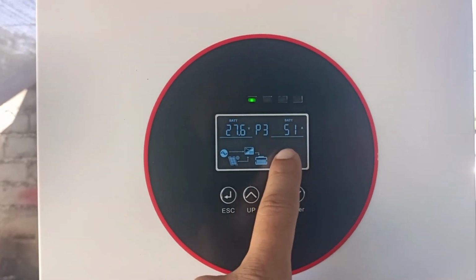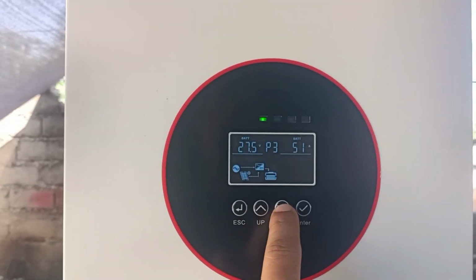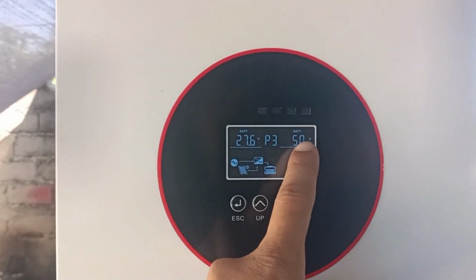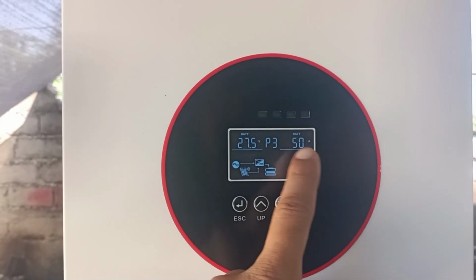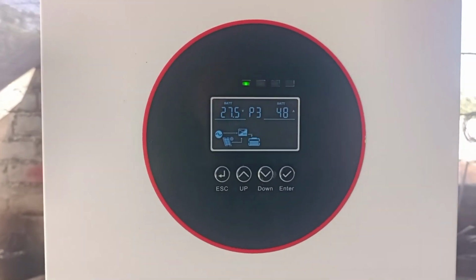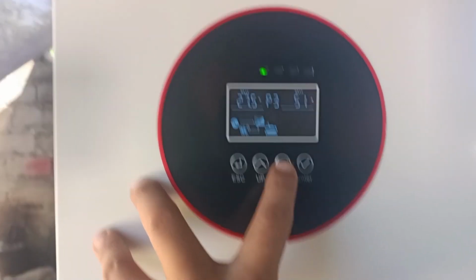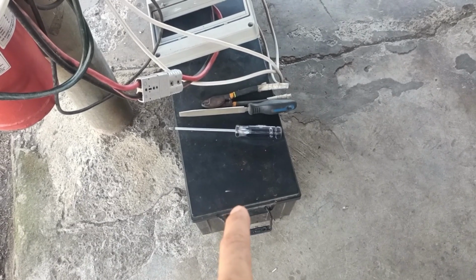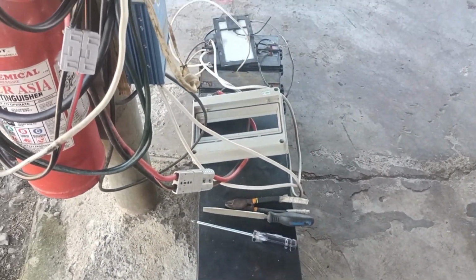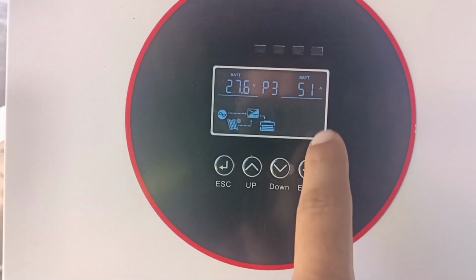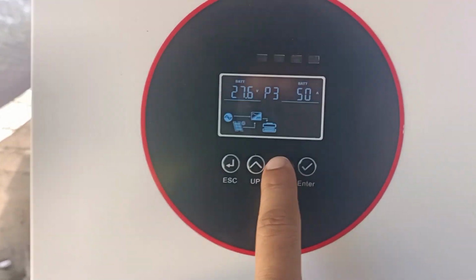Now the BMS is set to 50 amps also, so this 50 is limited by the BMS. This thing can push 100 amps. The capacity of this battery is 100 amp hour, and it's being charged at 50, which means the charge rate is 0.5C. 1C is 100 amp hour, so this is being charged at half a C, 0.5. That's how it works.